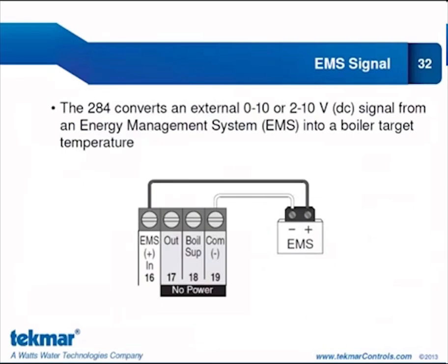One thing I do want to make clear is we use the term EMS a couple times on the 284. EMS is referred to the input we receive from an energy management system. EMS1 and EMS2 are outputs that we use to control boilers that require a temperature-based target. So keep that distinction clear in your mind, EMS versus EMS1 and EMS2, which are boiler outputs.